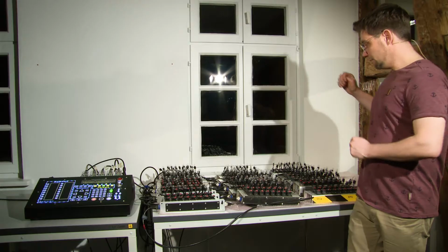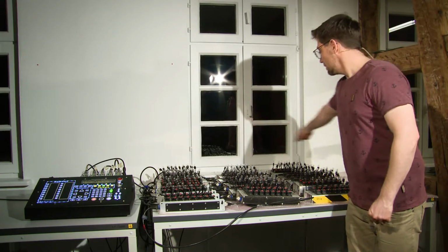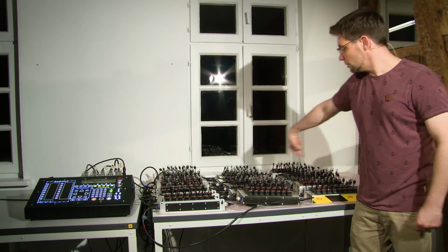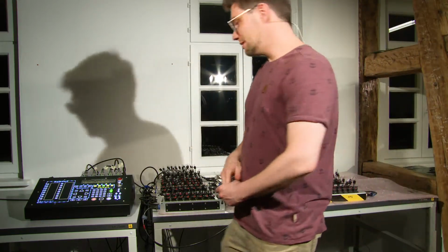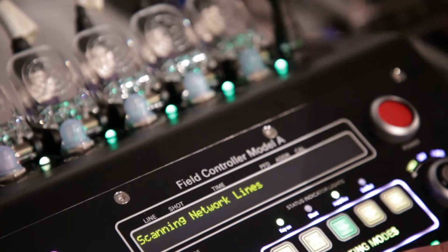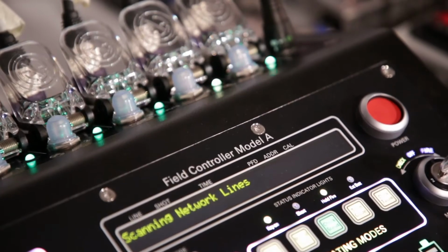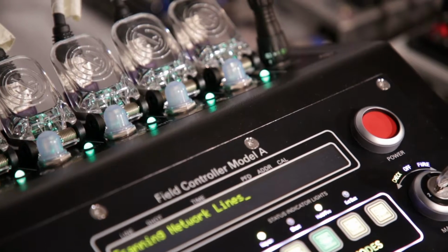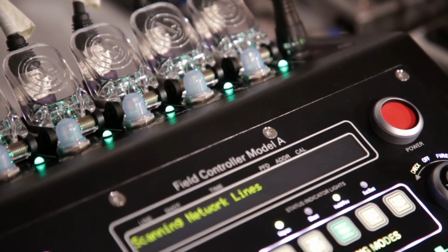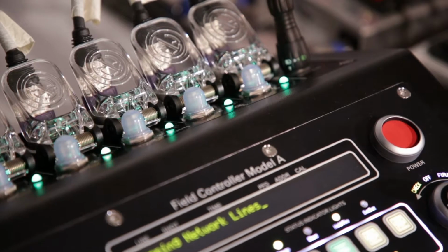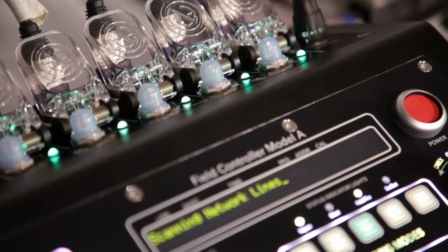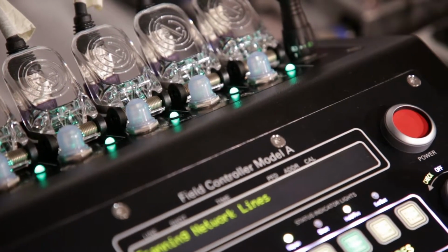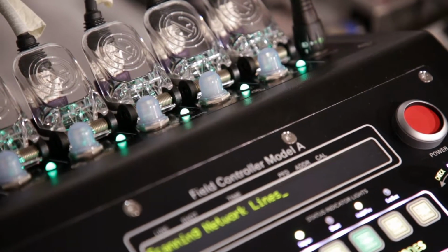So let's go over to the setup and scan a real network. We have here our 5 lines: line number 1 with 3 FMs, line number 2, line number 3, 4, and 5. And now we do the automated line assignment scan. Now you also see the yellow in the indicators on the outputs that tells you that it found the FMs there. Of course, we only have 15 modules connected, so all the rest of the scanning, since it goes up to 7F, is not finding anything in the higher address values.